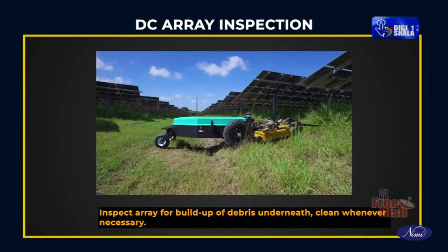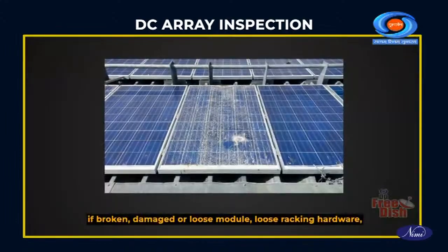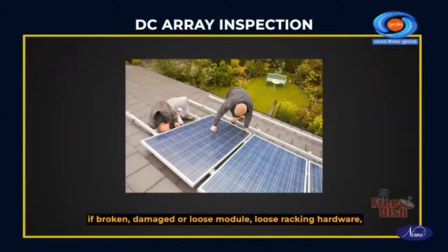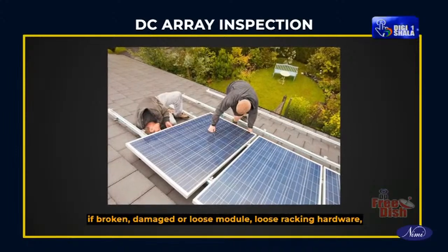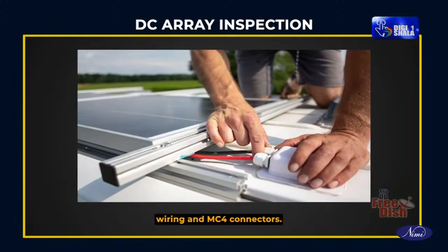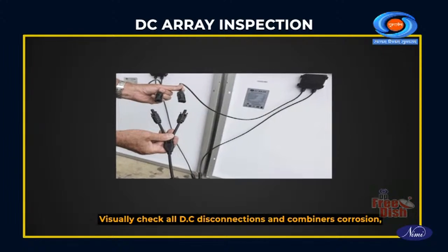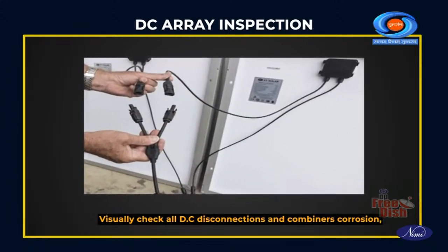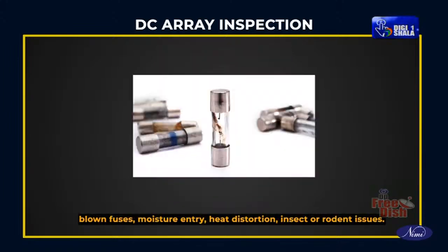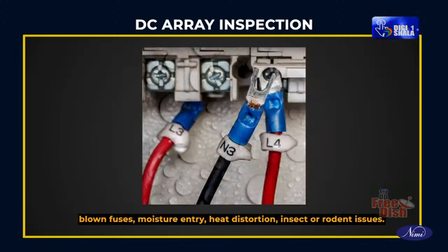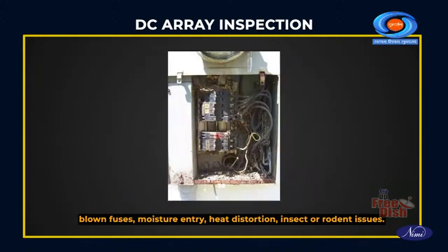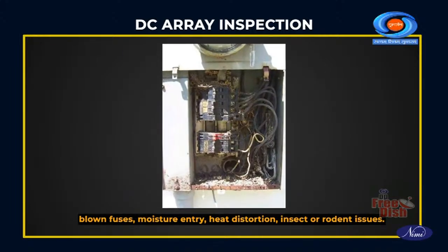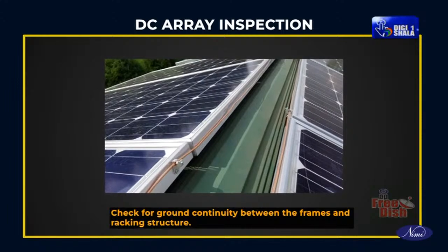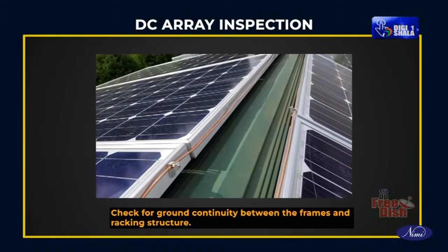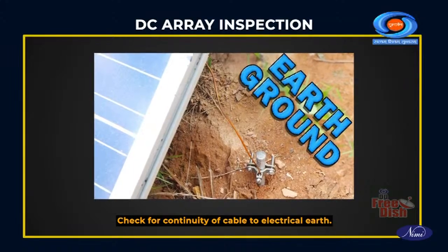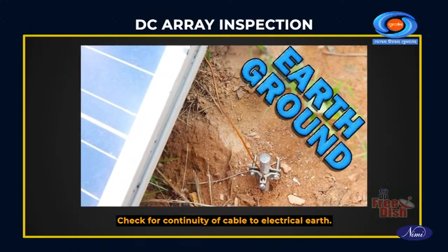Clean whenever necessary. Visually check the array. Look for broken, damaged or loose modules, loose racking hardware, wiring and MC4 connectors. Visually check all DC disconnections and combiner for corrosion, blown fuses, moisture entry, heat distortion, insect or rodent issues. Check for ground continuity between the frames and racking structure. Check for continuity of cable to electrical earth.